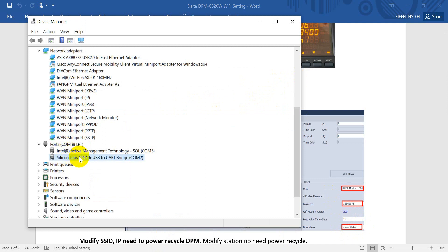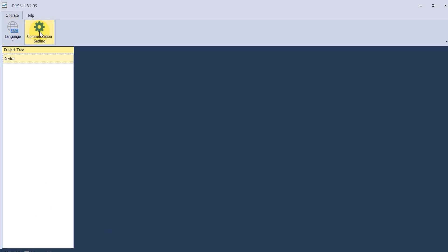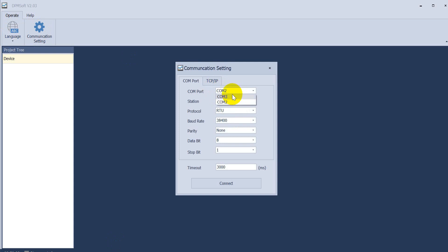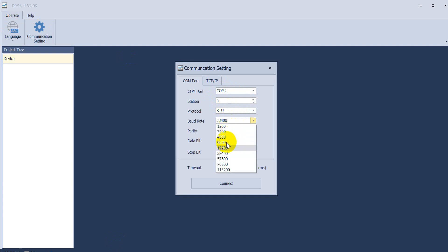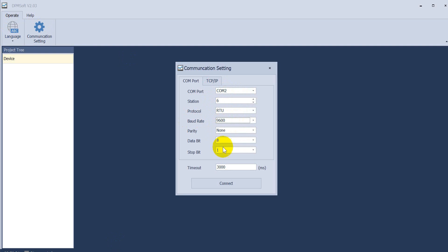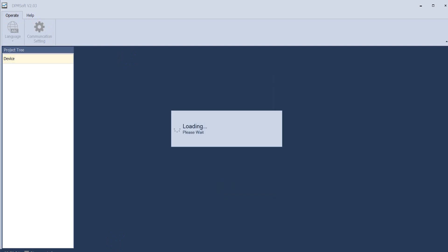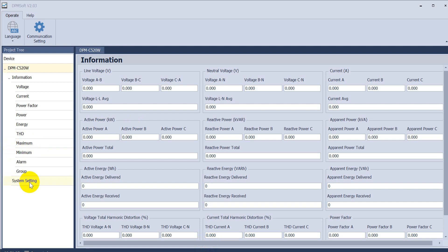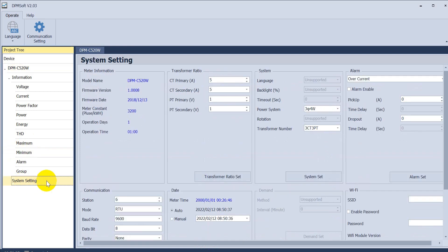Next, we will check the serial port and then go to the software portion. Here we select serial port 2 with station address 6, RTU. The baud rate is 9600 and format is 8-N-1, so we click connect. After we access, click system setting and you will see the firmware version information of this power meter.